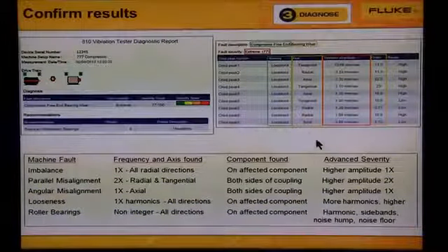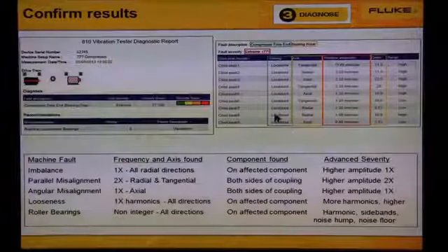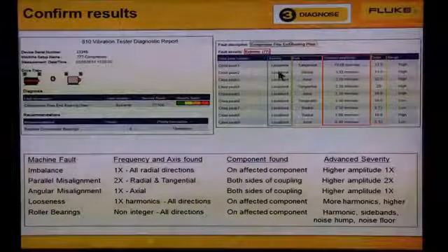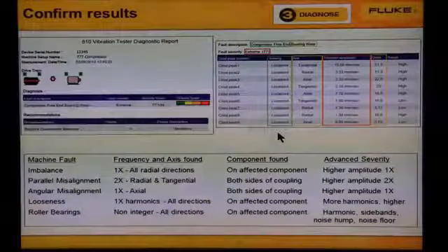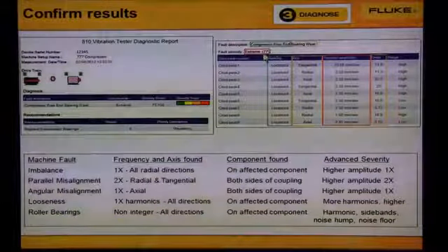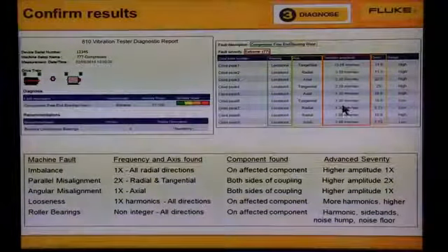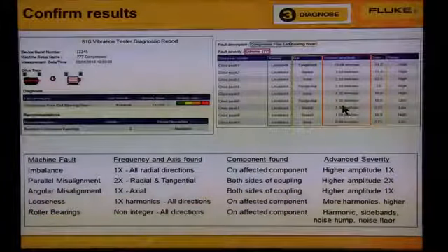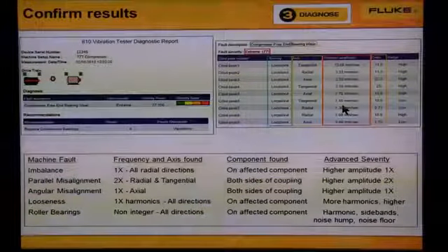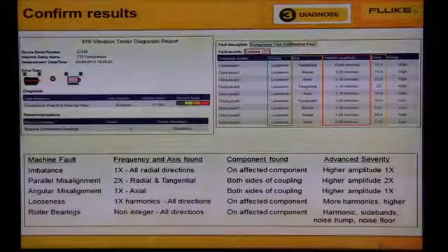The fault was found on the compressor free end, which is supported by location 4 under the bearing column. And the fault was extreme severity score of 77, which is supported by the high amplitude of the peaks under the vibration amplitude column. This confirms that the results are valid and we do have bad bearings.